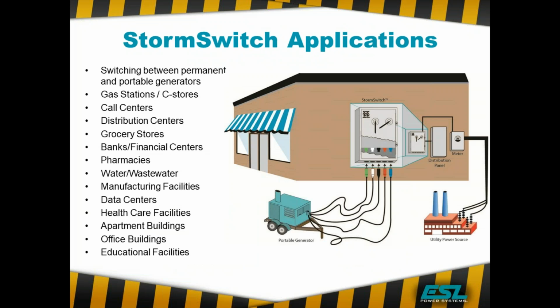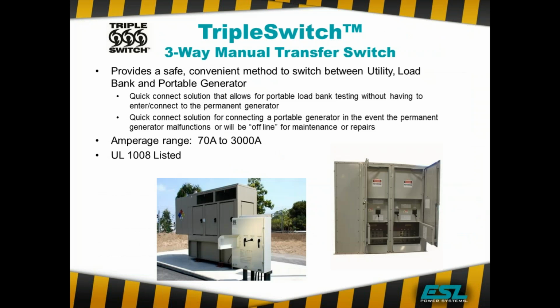So your storm switch applications, again, are switching between your permanent and portable generators, or anytime you need to bring in a portable generator to back up your facility and you don't have to have power instantaneously. So now let's talk about the triple switch. As you can see, the triple switch provides a means where you can switch between your portable generator, your permanent generator, and a load bank. So it provides all the functionality that you need to accomplish both of these functions, and provides a quick connect for all of that, and makes it very, very efficient, very, very cost effective.